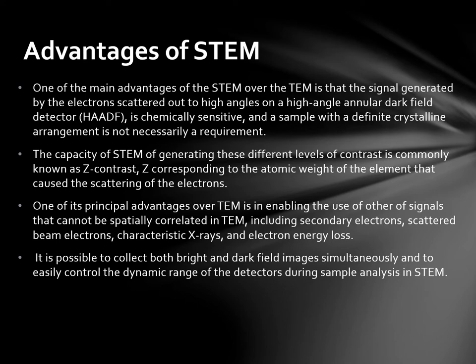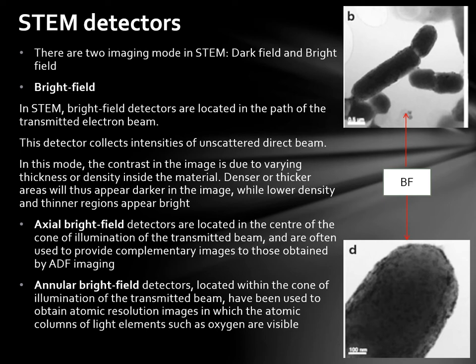There are two imaging modes in STEM: dark field and bright field. In STEM, bright field detectors are located in the path of the transmitted electron beam. This detector collects intensities of the unscattered direct beam. In this mode, the contrast in the image is due to varying thickness or density inside the material. Denser or thicker areas will thus appear darker in the image while lower density and thinner regions appear bright. Axial bright-field detectors are located in the centre of the cone of illumination of the transmitted beam and are often used to provide complementary images to those obtained by ADF imaging. Annular bright field detectors located within the cone of illumination of the transmitted beam have been used to obtain atomic resolution images in which the atomic columns of light elements such as oxygen are visible.